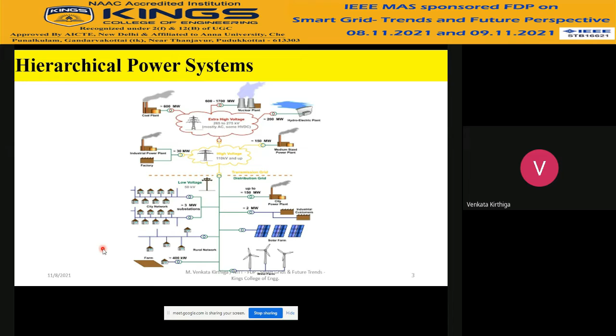Now, when you have utility grid, I have marked the 2 points as vulnerable points. How to understand these vulnerable points? Apart from this tie line, I can call this the tie line connecting this part of the system. If I say this is one half and this is the other part of the system, this line is actually the interconnection of these two systems. These two are initially considered to be a central utility power station with 600 megawatts each.